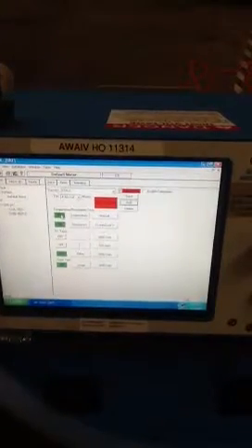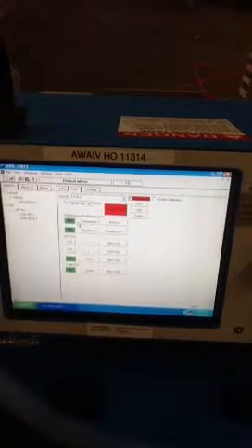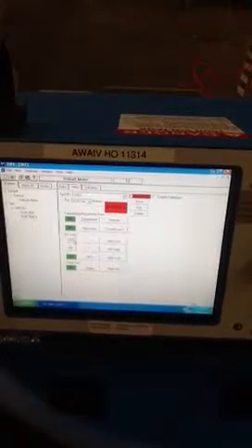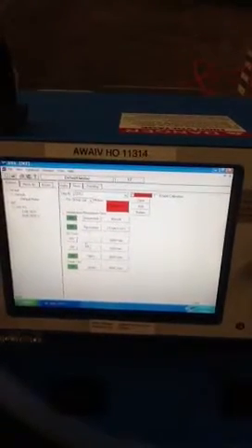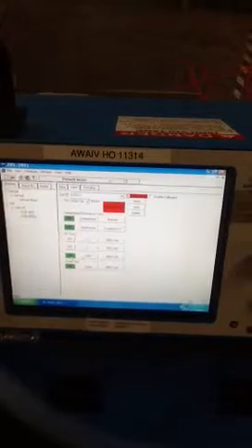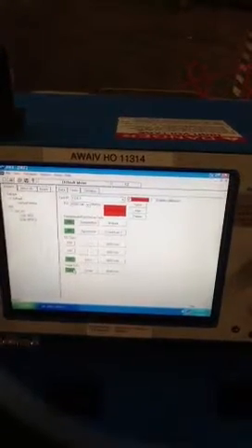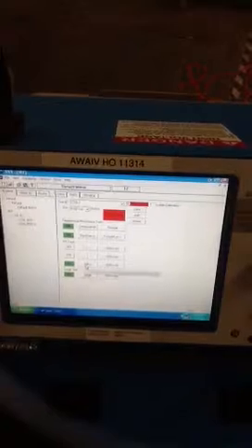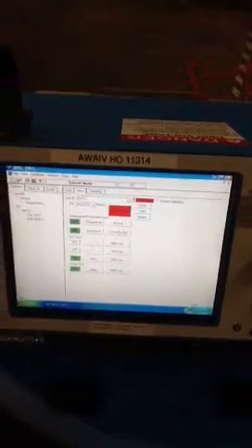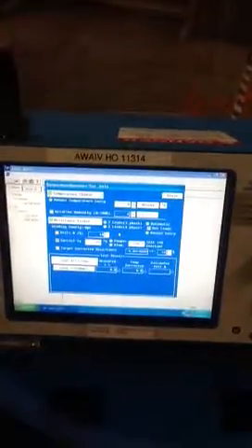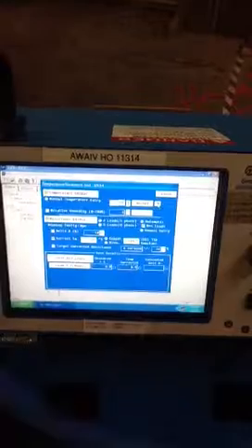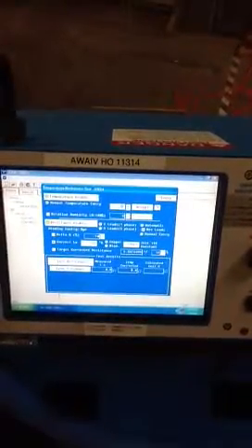First of all, we're going to go in here and turn on the temperature compensation, turn on the resistance, and turn off the mega ohm test and the DA or PI test. We're just going to perform a high pot test, and then the surge. This is a DC high pot test, not an AC high pot test. We're going to go into this button here, and then we're going to select Fahrenheit. So that means we will temperature compensate back to whatever temperature you enter into here.